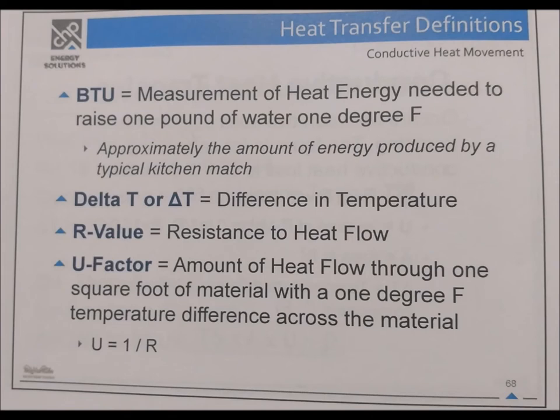BTU equals the measurement of heat energy needed to raise one pound of water one degree Fahrenheit — approximately the amount of energy produced by a typical kitchen match. Delta T equals the difference in temperature. R-value equals the resistance to heat flow. The U-factor equals the amount of heat flow through one square foot of material with a one degree Fahrenheit temperature difference across the material. U equals 1 divided by R.